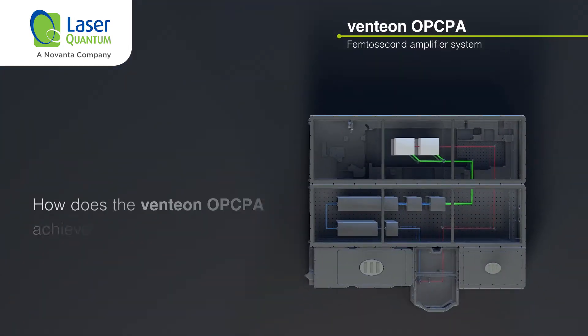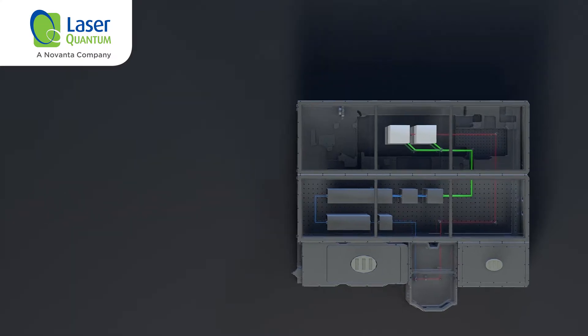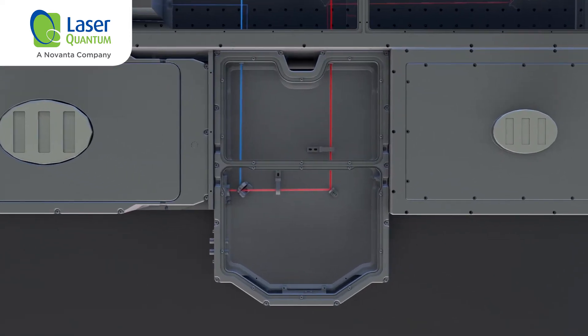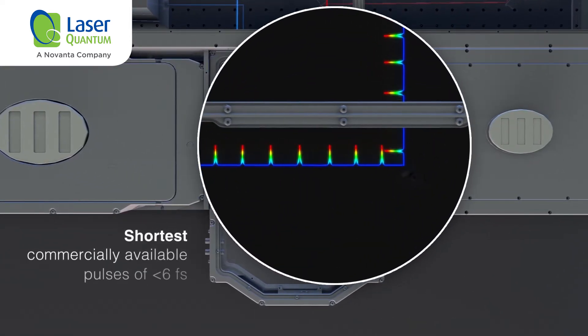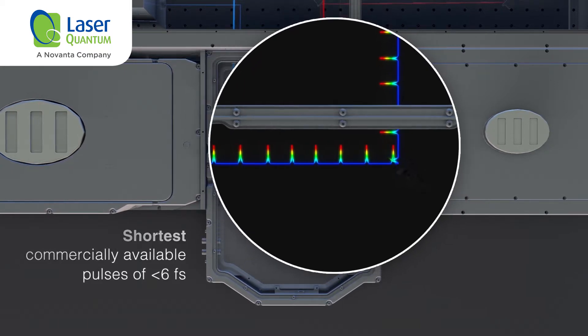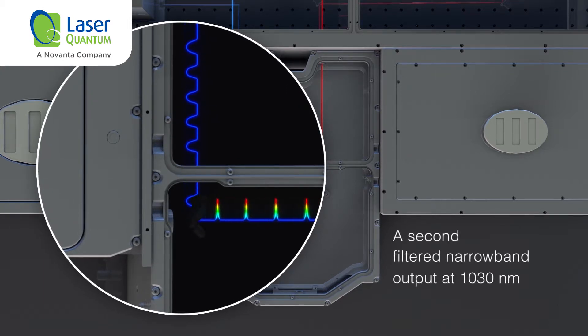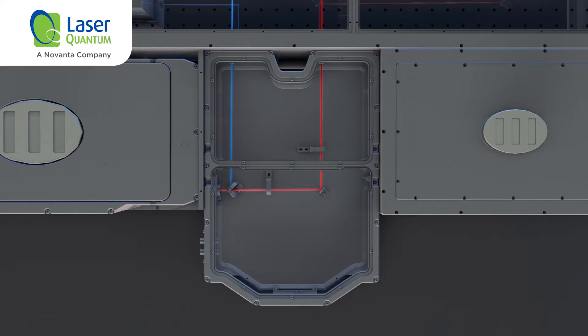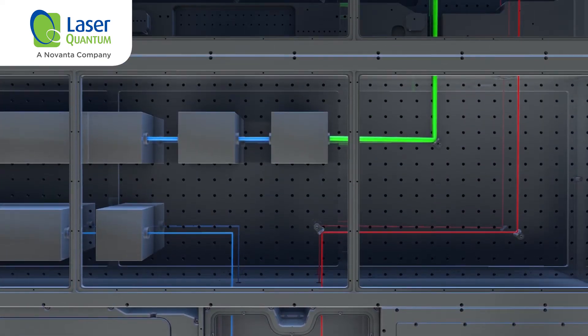But how does the venteon OPCPA achieve this? The process starts with the venteon dual laser, which produces an octave-spanning output that supports the shortest commercially available pulses of less than 6 femtoseconds. A second narrowband output at 1030 nm is filtered from the main beam to create a synchronous seed for the amplifier, making it ideal for CEP stabilization.